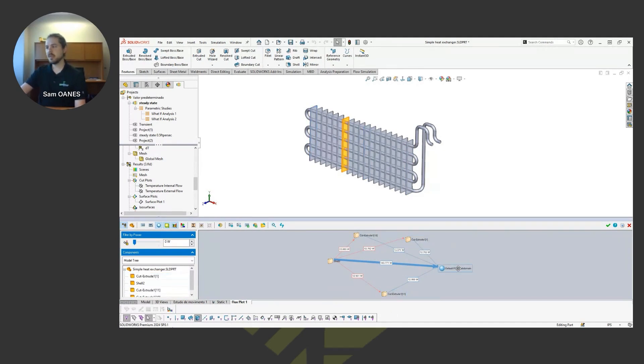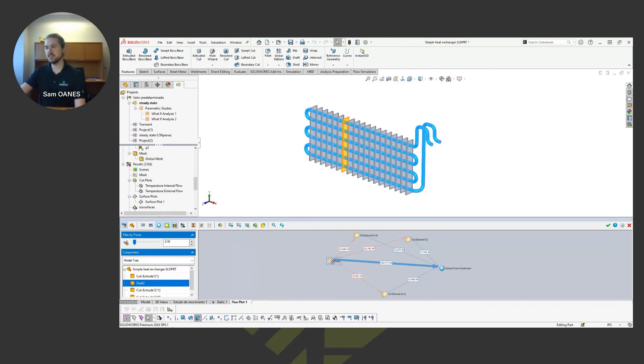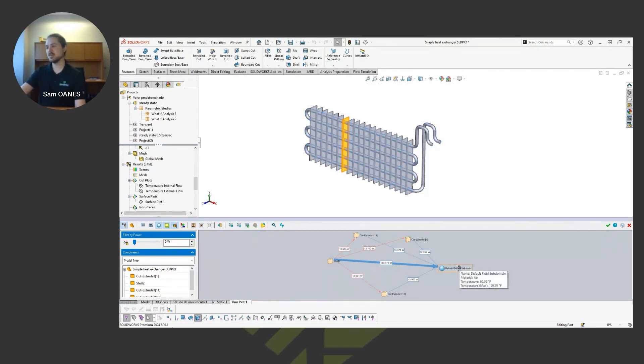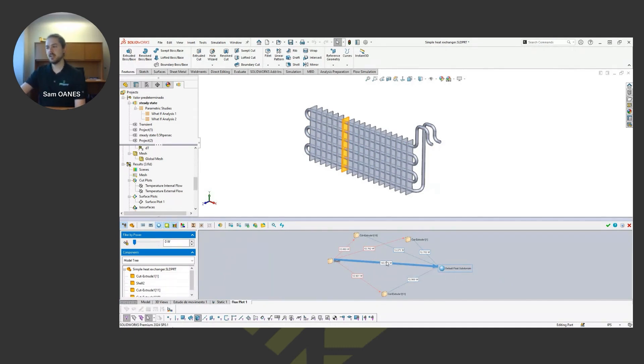And then how much is it losing to the default domain. So we can see that that pipe is losing 143 watts just out to the default, that air fluid subdomain. So that's telling us that's just due to convection from that 50 mile an hour wind load. Most of the cooling effect is coming from that, not so much being lost through the plates.